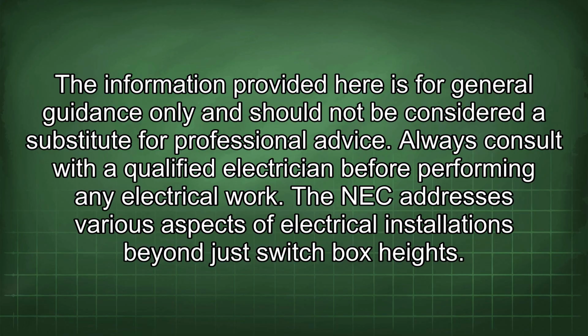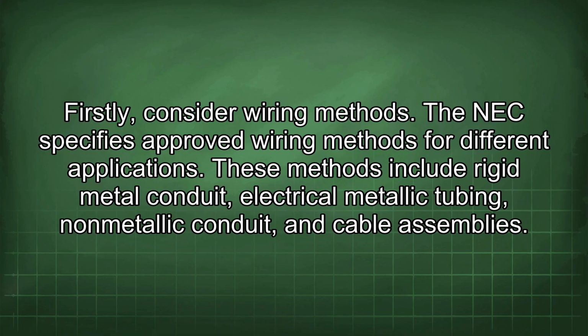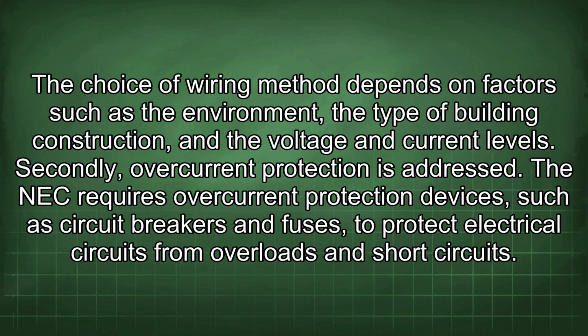The NEC addresses various aspects of electrical installations beyond just switchbox heights. Firstly, consider wiring methods. The NEC specifies approved wiring methods for different applications. These methods include rigid metal conduit, electrical metallic tubing, non-metallic conduit, and cable assemblies. The choice of wiring method depends on factors such as the environment, the type of building construction, and the voltage and current levels. Secondly, overcurrent protection is addressed.